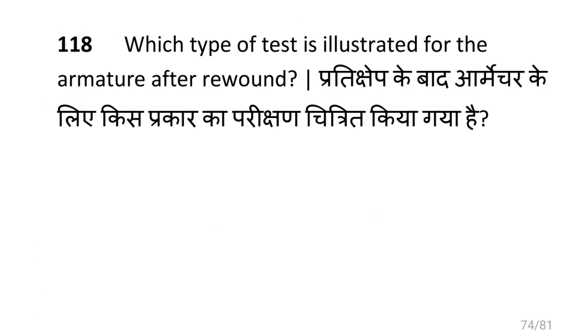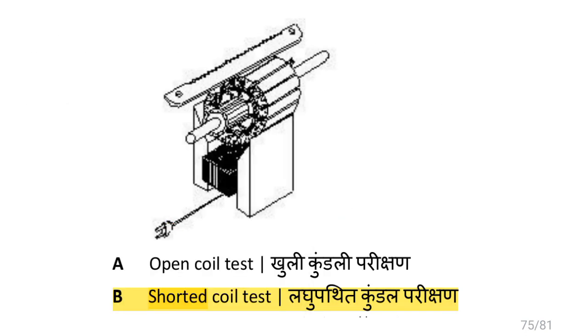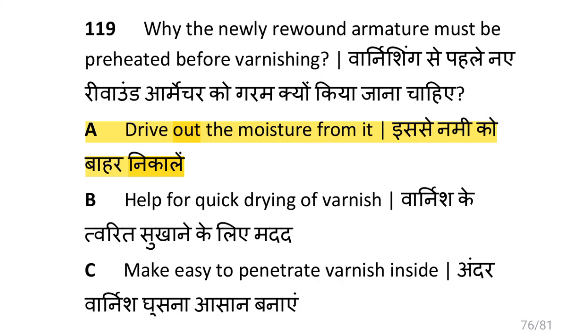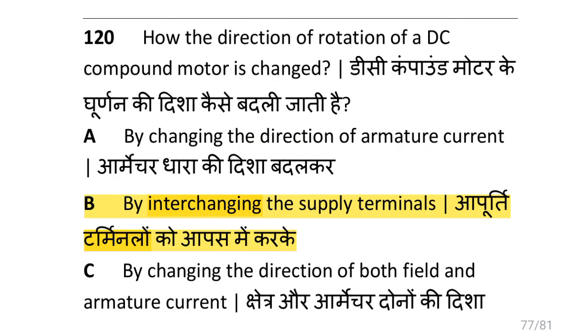Which type of test is illustrated for the armature after rewinding? That is shorted coil test. Why must the newly rewound armature be preheated before varnishing? To dry out the moisture from it. How is the direction of rotation of a DC compound motor changed? By changing the direction of armature current.